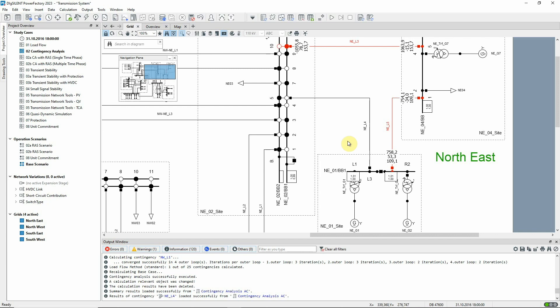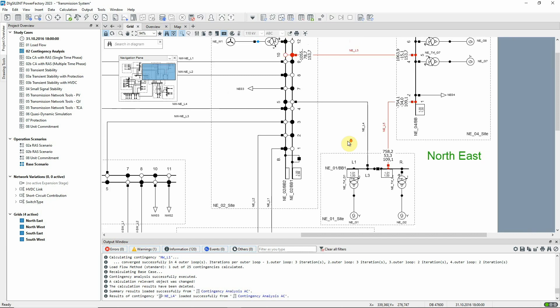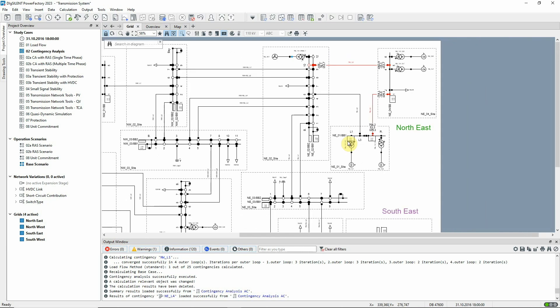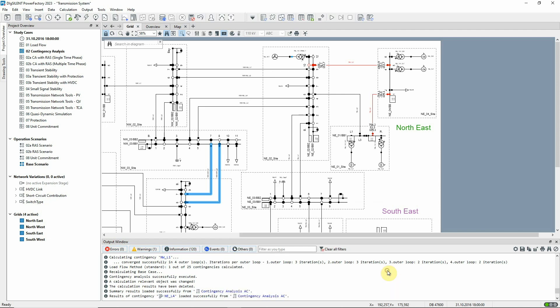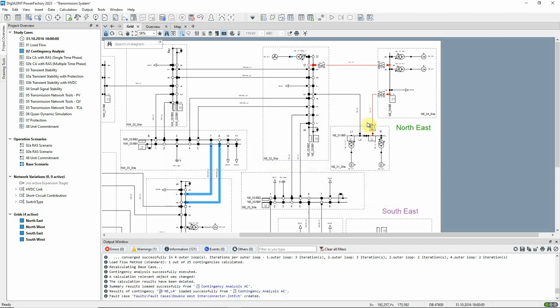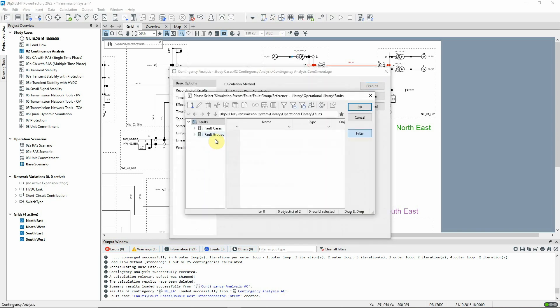Customized fault cases can also be defined and a simple way to do this is from a graphic. As an example, we can create a double circuit fault on these circuits which form the interconnection between the north-west and south-west grids. The name can be changed as required, and the new contingency can be selected to run in our contingency analysis.